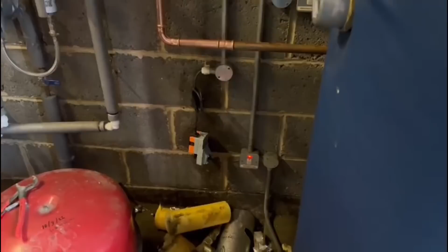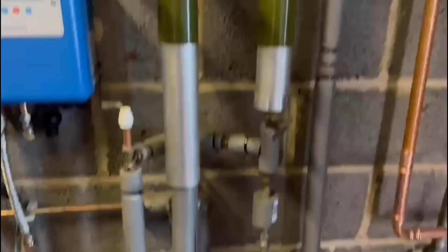So from the microfill, we're going to have a cold main from here into the flex. We're going to go out back onto this copper here, which is the old feed. That then goes up and into the top. I've then also cut an AAV in because that's going to be the highest part of that section. Going round, flows now attached onto the boiler. So that's the pump, and that is controlled by the boiler. Return is also connected. I will put an AAV there, so then any air in the boiler on that section can vent there, and that's into the boiler there.